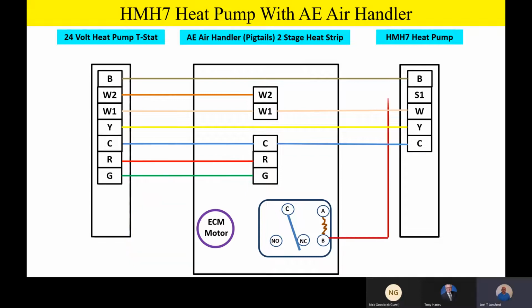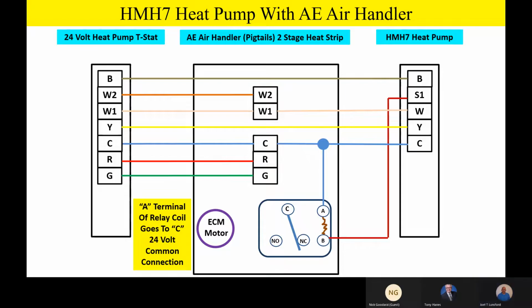Now, if we take a look at that airflow reduction relay, the B terminal, or one side of the relay coil, is going to go up to the S1 outside. And what that's going to do, that's going to allow us to reduce airflow when the outdoor unit is at a lower point of modulation. The other side of that single pole double throw relay, the coil is going to go to 24-volt common to complete that coil circuit.